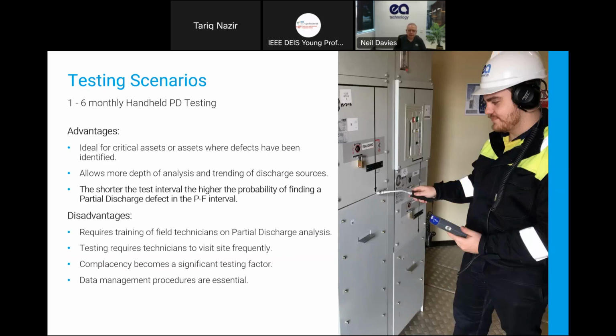So let's say that we decide that we need to increase that frequency. So we've got a higher criticality asset, for example. So we're going to test every 1 to 6 months, every 6 months, every 3 months, whichever it may be, to reduce that probability. That's the sort of thing that we would do if you've done a spot check, you found a defect, and you don't think that defect is of a level where you need to act today. Then you would introduce an intermediary regime of testing to look for trending discharge sources. The shorter the test interval, the higher the probability of finding the PD before it hits failure, and finding that defect and understanding it. Of course, you're putting people in the field more frequently again, so you still need the technicians. They're going to have to be in there, so it's slightly more costly.